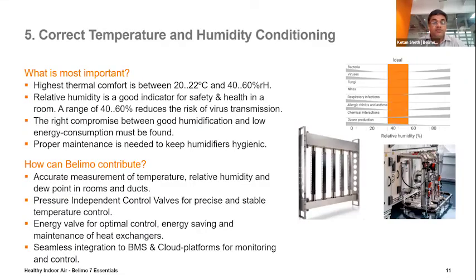Correct temperature and humidity conditioning, as we discussed. On the right hand side, you can see the gist of findings, where when the humidity is between 40 to 60%, there is less likelihood of virus spreading. So the control should be in that range, or the room should be under that humidity area. Similarly, a temperature between 20 to 22 or 24 degrees Celsius is highly safe and healthy. It does not promote or support the spread of virus transmission.